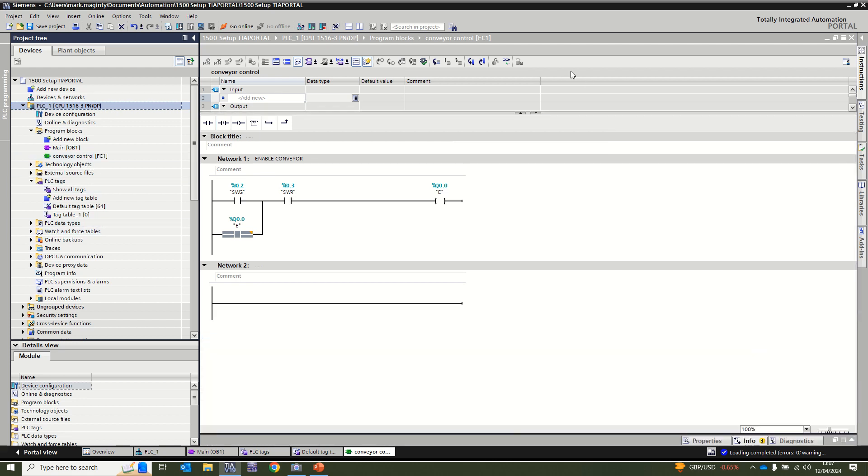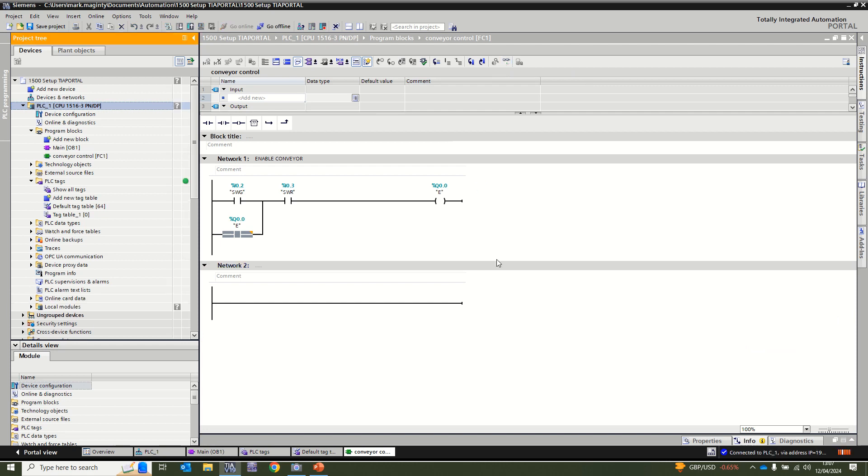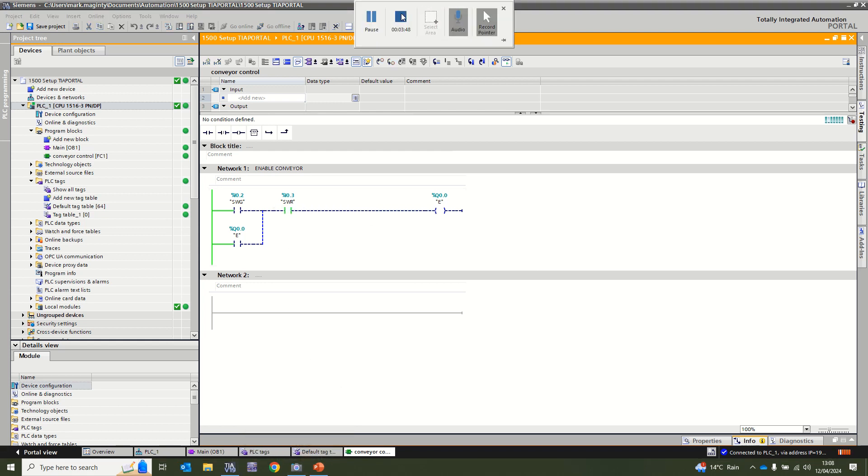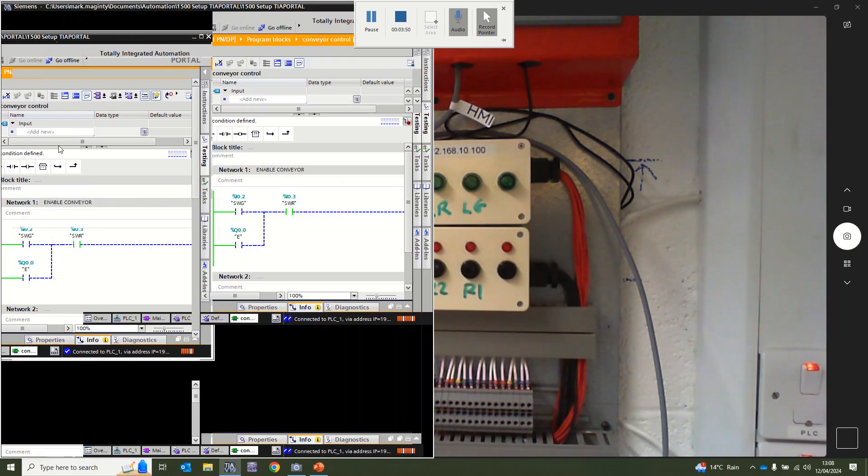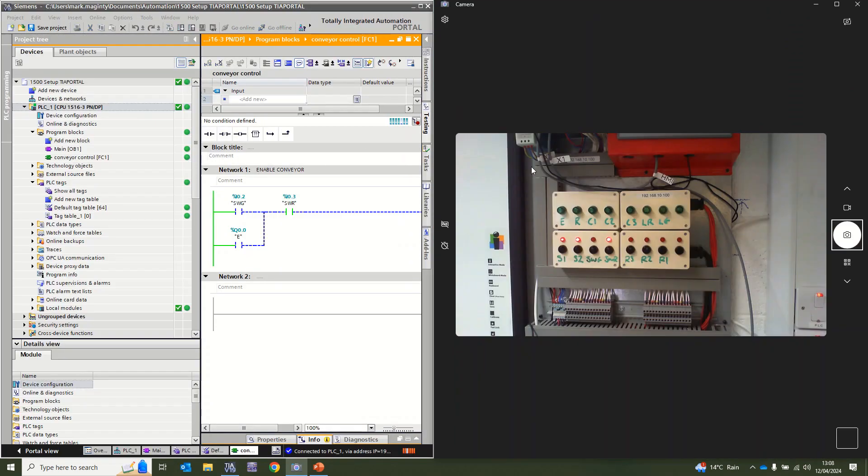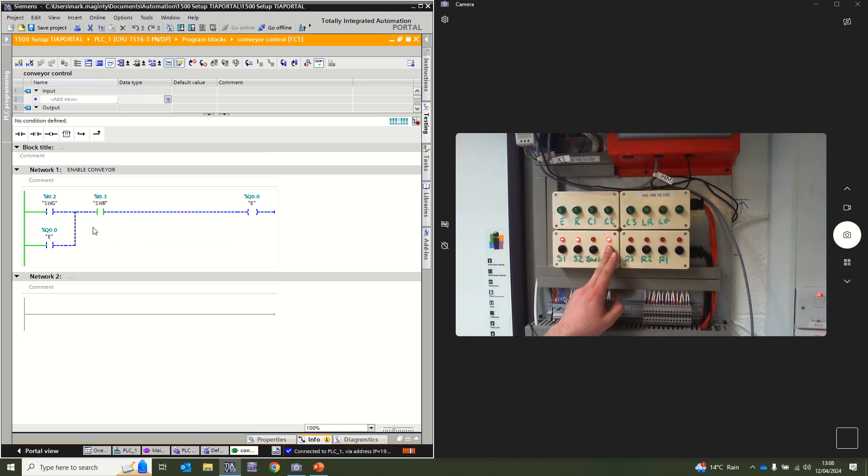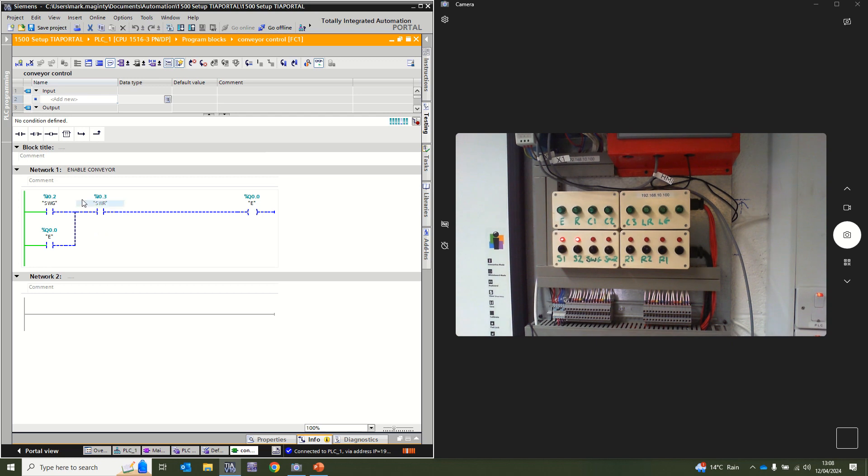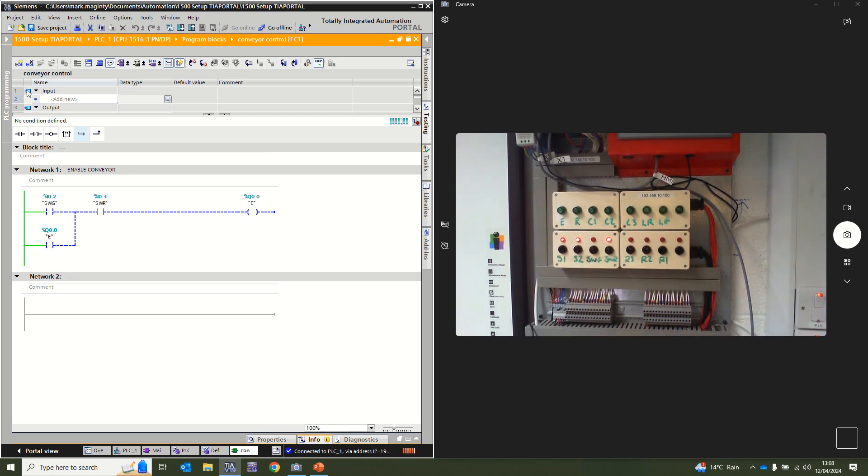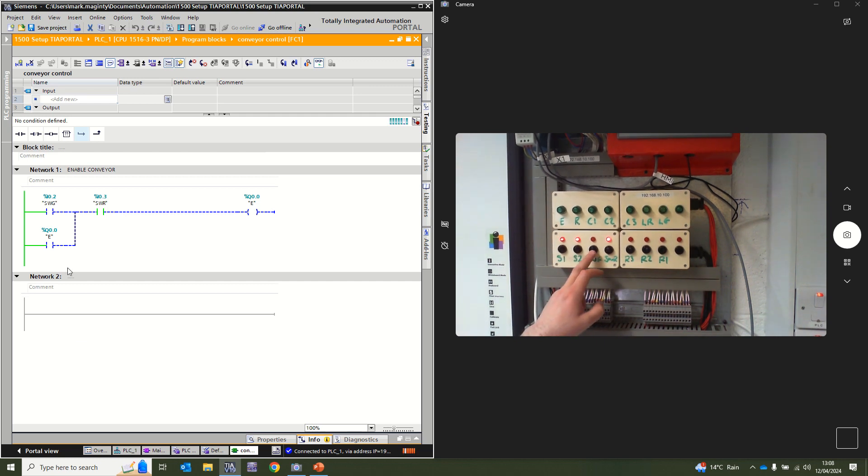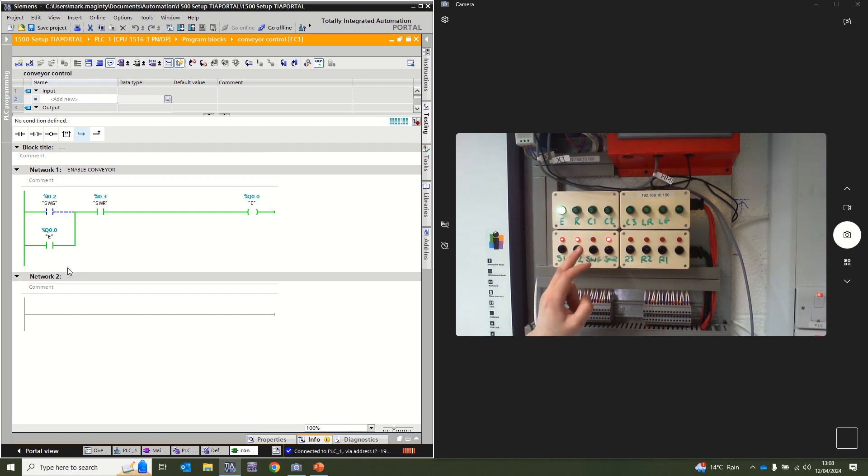We will then go on to monitor mode and we can see currently that SWR is on. If I operate SWR as you see here going into the position, we lose that I0.3 here, so we're going to keep it on mimicking what the real push button will be doing. That means if we press SWG, when we press it we see obviously I0.2 becomes active and the output E. If I let go we see that E has maintained itself on and will only go off when I press the SWR.